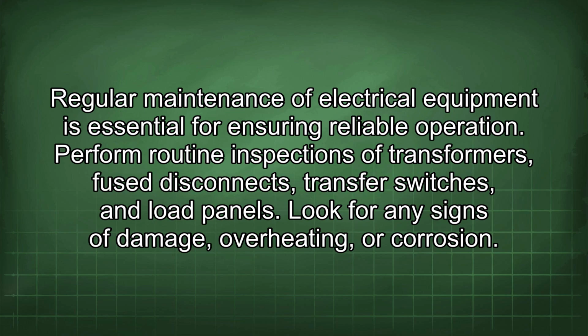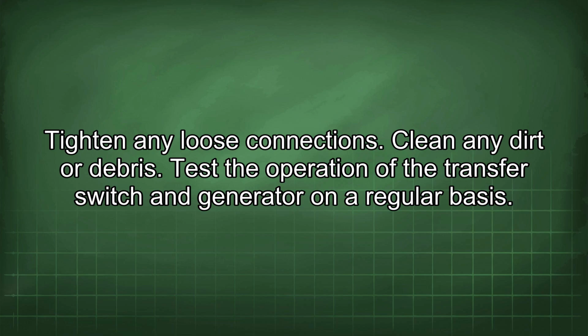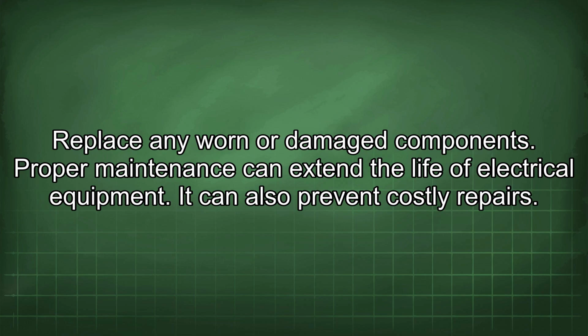Regular maintenance of electrical equipment is essential for ensuring reliable operation. Perform routine inspections of transformers, fused disconnects, transfer switches, and load panels. Look for any signs of damage, overheating, or corrosion. Tighten any loose connections. Clean any dirt or debris. Test the operation of the transfer switch and generator on a regular basis. Replace any worn or damaged components. Proper maintenance can extend the life of electrical equipment. It can also prevent costly repairs.